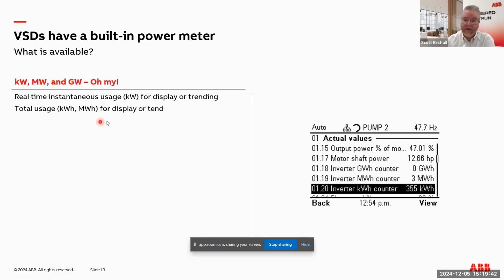I can also look at kilowatts or megawatts. So right here, screenshot, I can see that this particular drive has consumed 3.355 megawatts of power since it's been installed, which this particular drive has probably only been operating for about 6 months because this is a new building. So what these are really nice is I can read information from the drive. I can read that daily if I want, and then I can record that through my building automation system, and I can rewrite it back to 0, and then I can record it the next day after 24 hours. I can do it weekly. I can do it monthly and then reset these counters. I don't have to reset them at all. There's a lot of different strategies there.